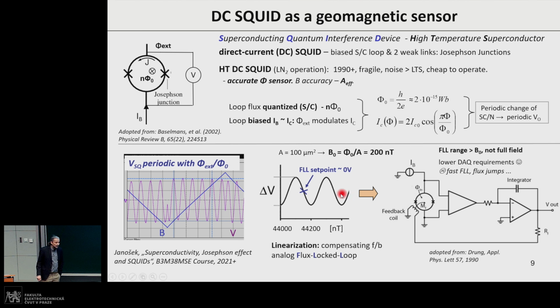So we are employing the classical trick how to linearize the sensor: to use a compensating feedback flux loop. We will choose the set point somewhere with the highest derivation, and with this simple, basically I controller, we can compensate the measured field, we can compensate the flux threading the SQUID, and read out the current needed to compensate such flux. This is the big advantage of the SQUID, because we can have much lower requirements on the data acquisition, because our FLL range can be only few quantums, for example, 400 nanotesla or 1 microtesla easily. The rest of the flux is basically frozen. There are some disadvantages. So, for example, the flux loop must be very fast, because the SQUID is sensitive up to terahertz.